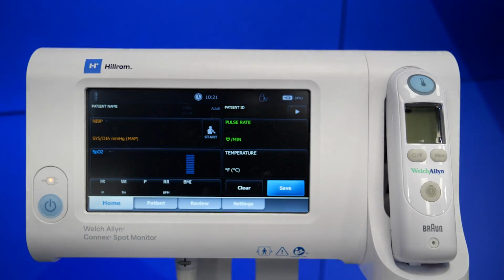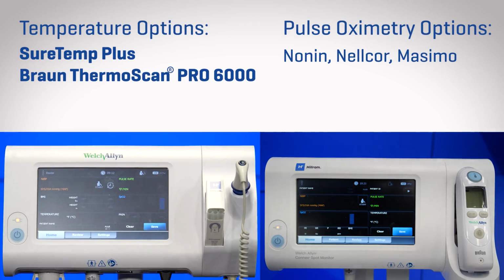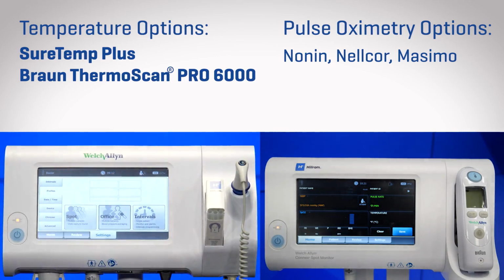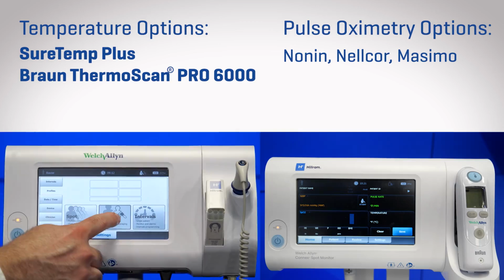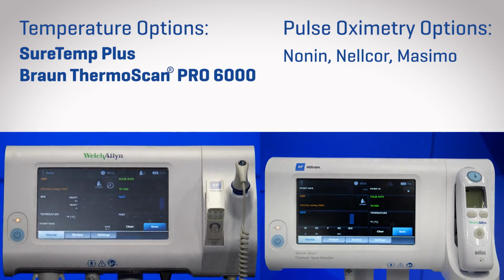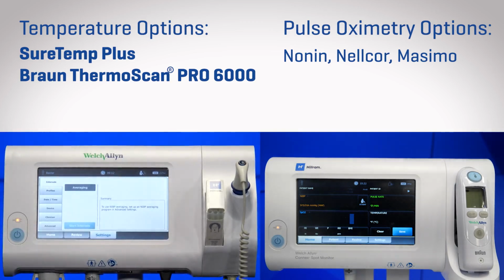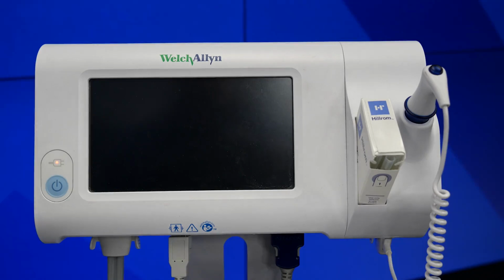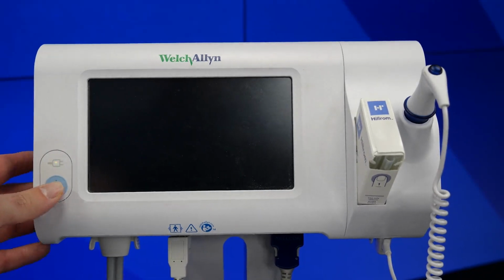The device comes standard with our SureBP non-invasive blood pressure technology, which measures the patient's BP on the inflation of the cuff. It can also be configured with different temperature and pulse oximetry options. Temperature options include oral, axillary, and rectal with the Welch Allyn SureTemp Plus, or tympanic with the Braun Pro 6000. Pulse oximetry can be configured to accept sensors from either Nonin, Nellcor, or Masimo. Now let's review the physical device and the software user interface.